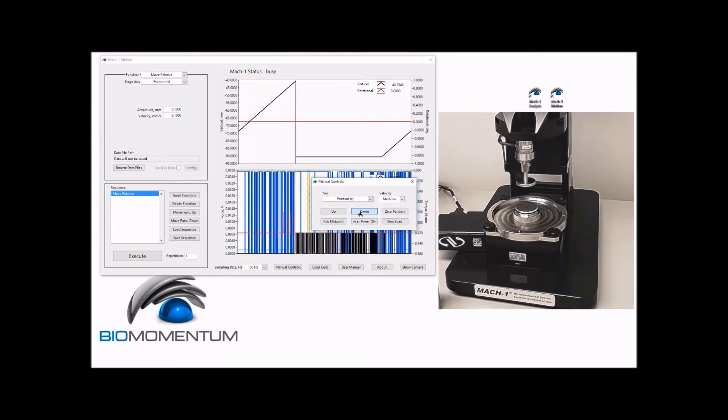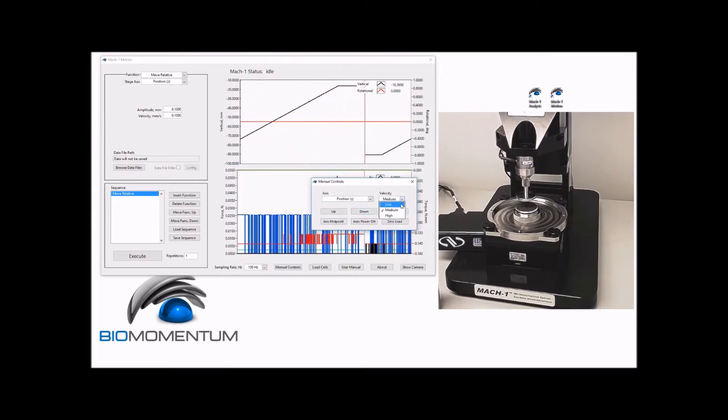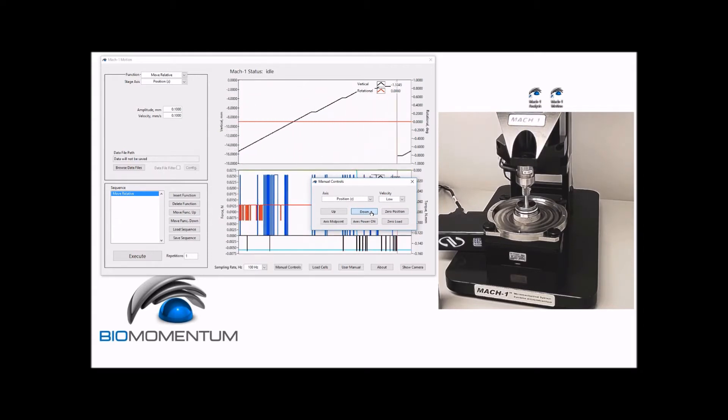Screw the sample holder onto the testing chamber. Using manual controls, lower the stage at medium speed to approximately 20 mm above the sample holder and lower the stage at low speed to approximately 2 mm above the sample holder.